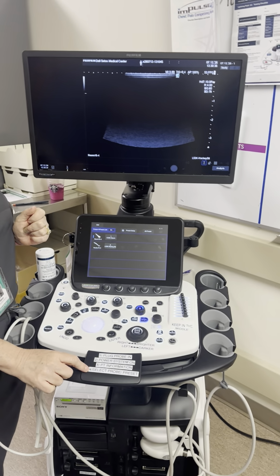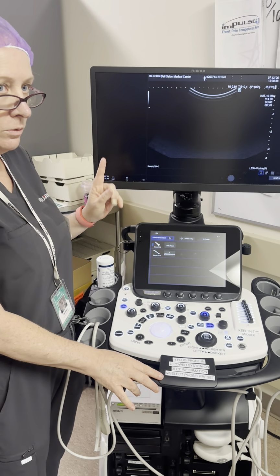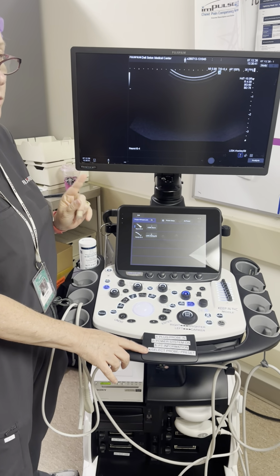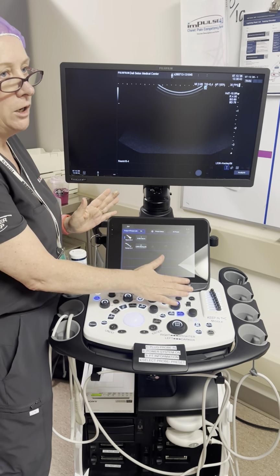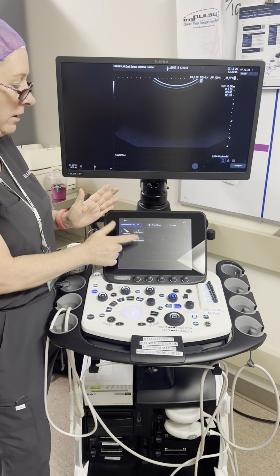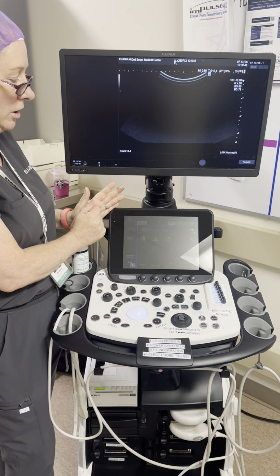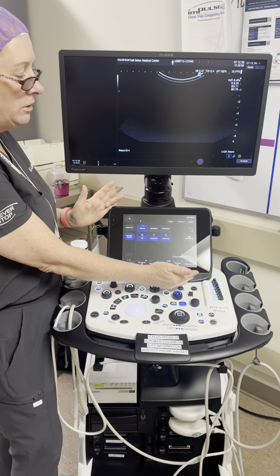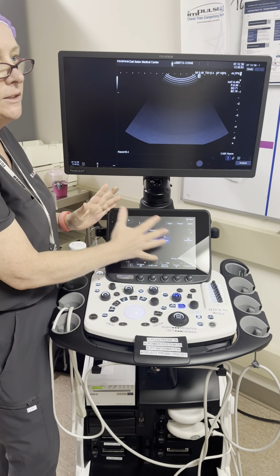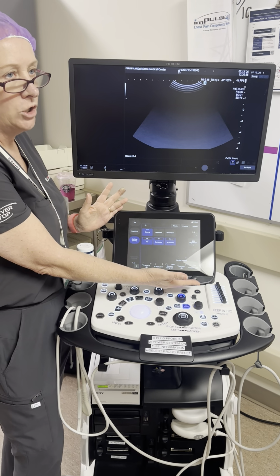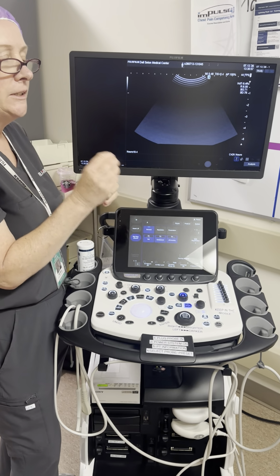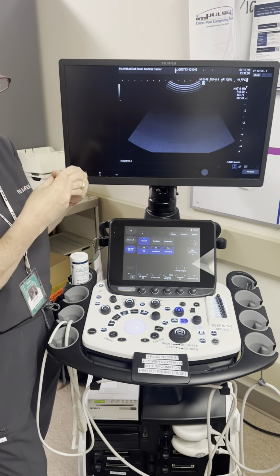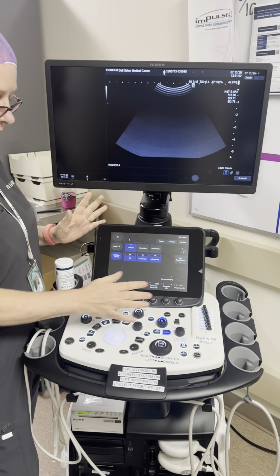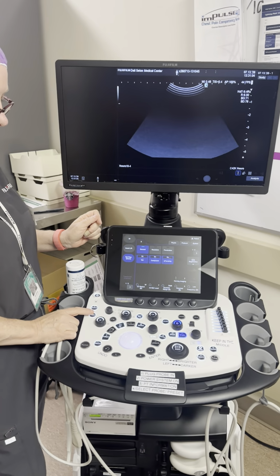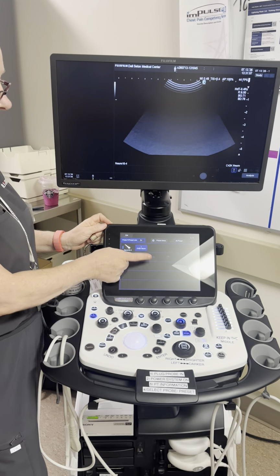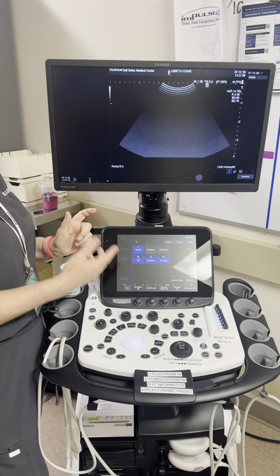And then number 4, if you're going to remember anything besides don't use pre-cleanse, number 4 is select the probe and preset. Don't leave the touch screen looking like this, okay? Make sure that you touch the preset so that the touch screen looks like this, because this is where all your options are to adjust the probe, and the settings that the doctor wants that are set up for that probe are in the preset. So if you wanted to go back out to the probe page, you can hit the probe button and you can select the other probe.